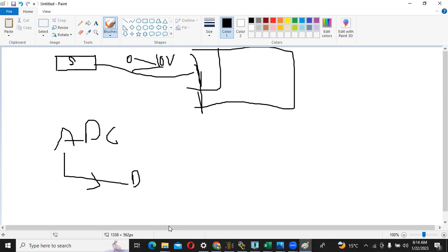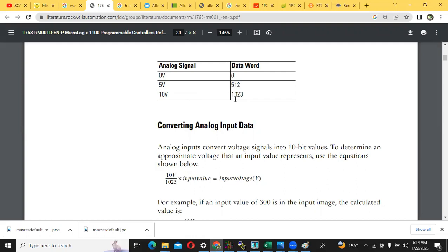In MicroLogix 1100, if analog signal coming from the sensor is 0 volt, it will be converted into 0. If it is 5 volt, it will be converted into 512. If it is 10 volt, it will be 1023. So if it will be 3 volt or 2 volt, then according to this ratio, the voltage will be. I make this ratio.